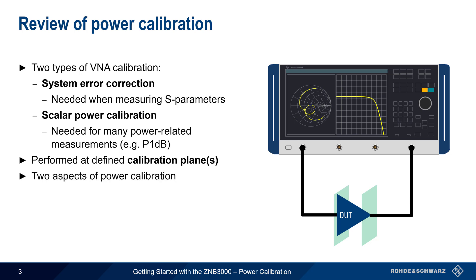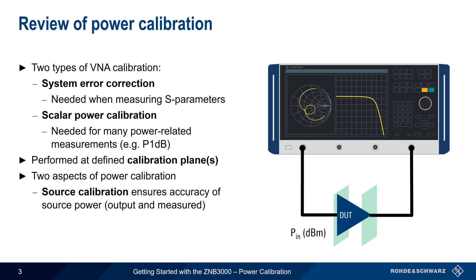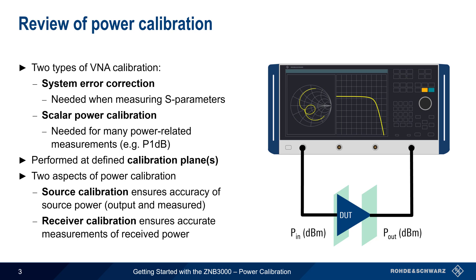There are two general categories of power calibration. Source calibration ensures the accuracy of both the source or stimulus power, as well as the accuracy of the measurement of this power. Receiver calibration, on the other hand, ensures that the received power is being accurately measured. We'll go through how to configure and run power calibration on Rohde & Schwarz's ZNB3000 series Vector Network Analyzers.